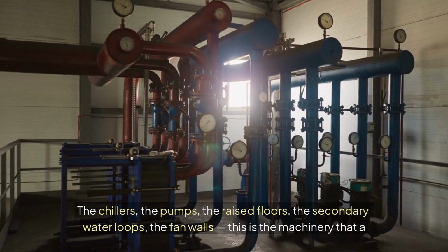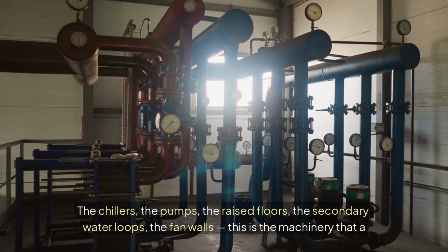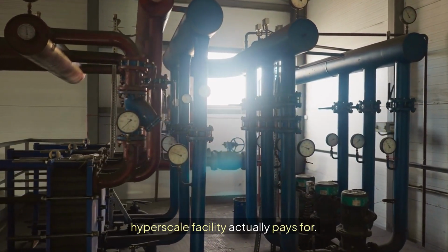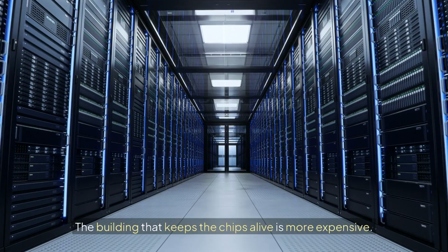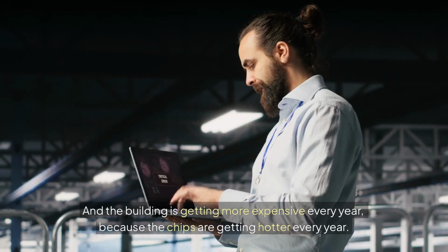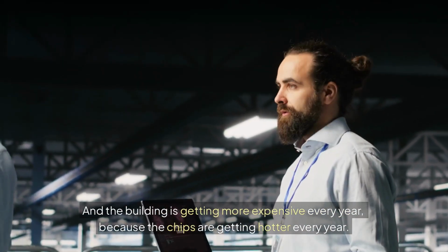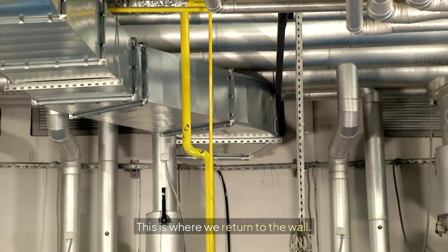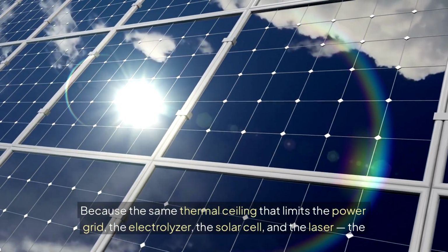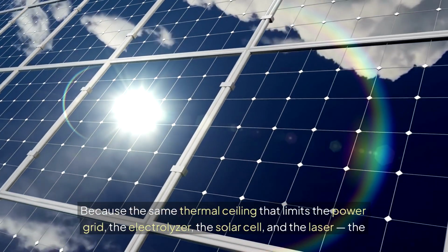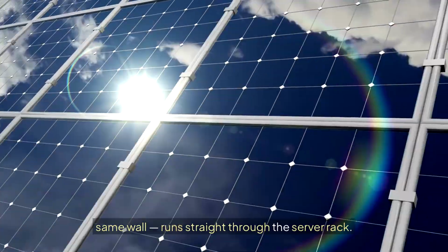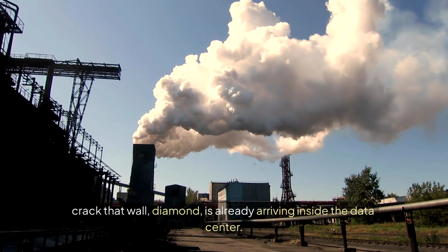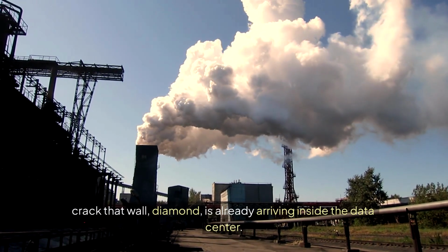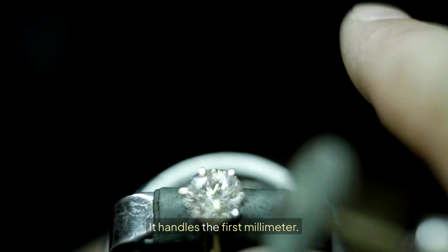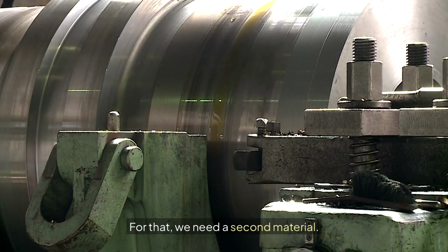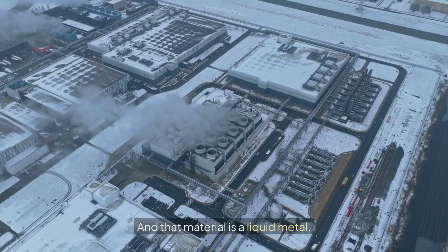The chillers, the pumps, the raised floors, the secondary water loops, the fan walls. This is the machinery that a hyperscale facility actually pays for. The chips are expensive. The building that keeps the chips alive is more expensive. And the building is getting more expensive every year because the chips are getting hotter every year. This is where we return to the wall. Because the same thermal ceiling that limits the power grid, the electrolyzer, the solar cell, and the laser, the same wall, runs straight through the server rack. And the material that Part 1 identified as the means to crack that wall, diamond, is already arriving inside the data center. But it arrives alone. It handles the first millimeter. It does not handle the next meter. For that, we need a second material. And that material is a liquid metal.